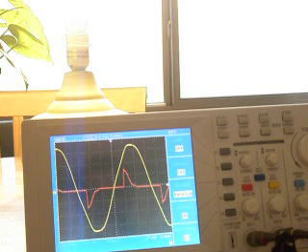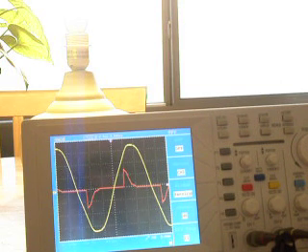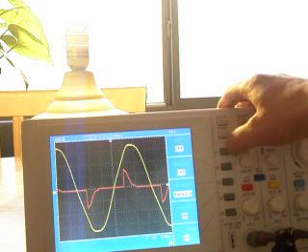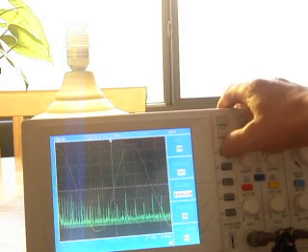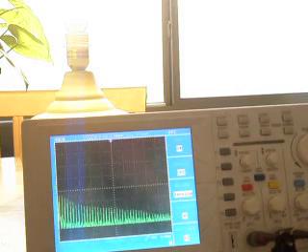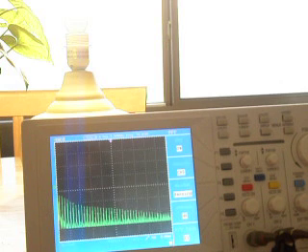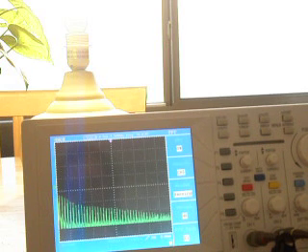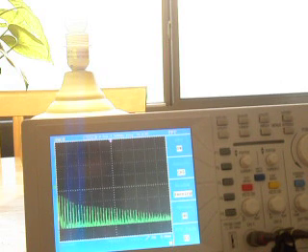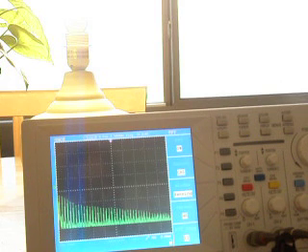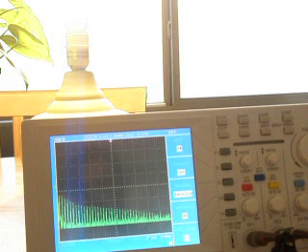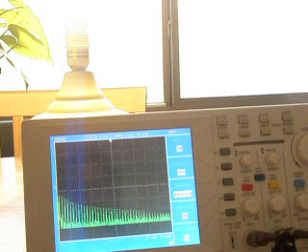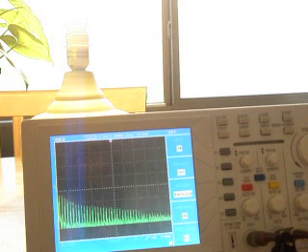And I'm going to show you that. Now we're going to go into what's called the fast Fourier transform, and that is what harmonics looks like. So normally the power system's running at 60 hertz, and if you have linear loads, resistive loads like normal light bulbs, you'd only see one spike. But because this is a non-linear load...